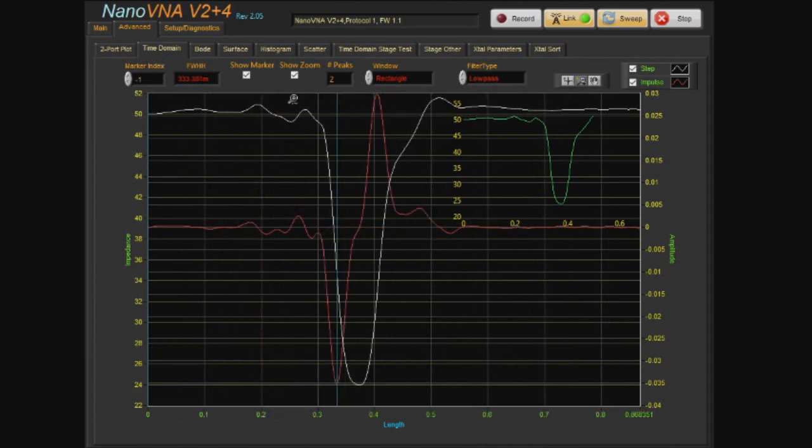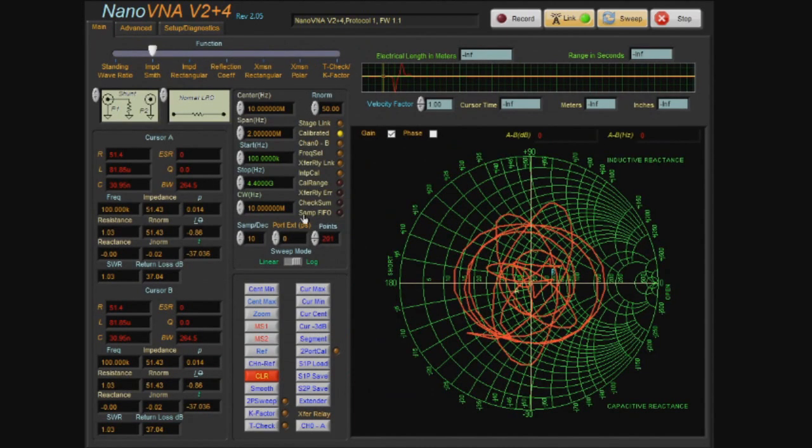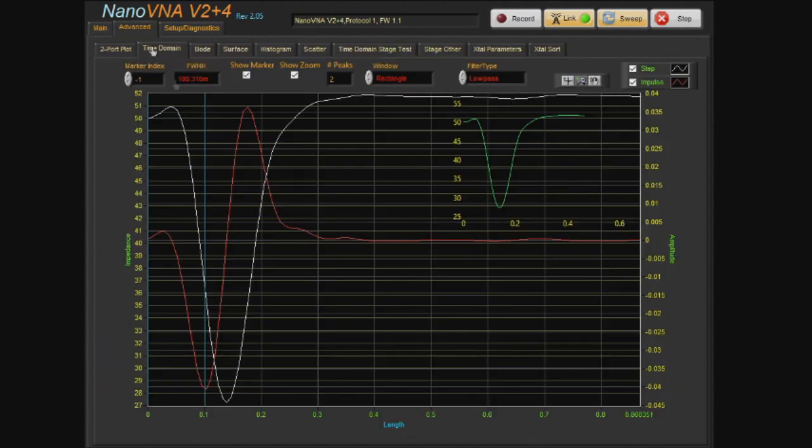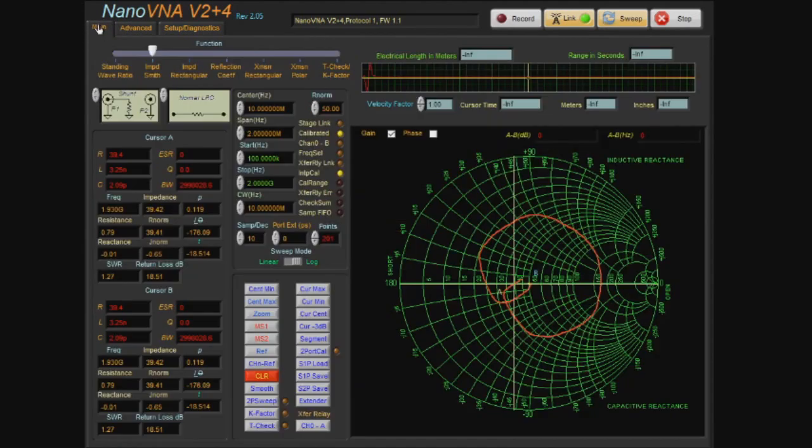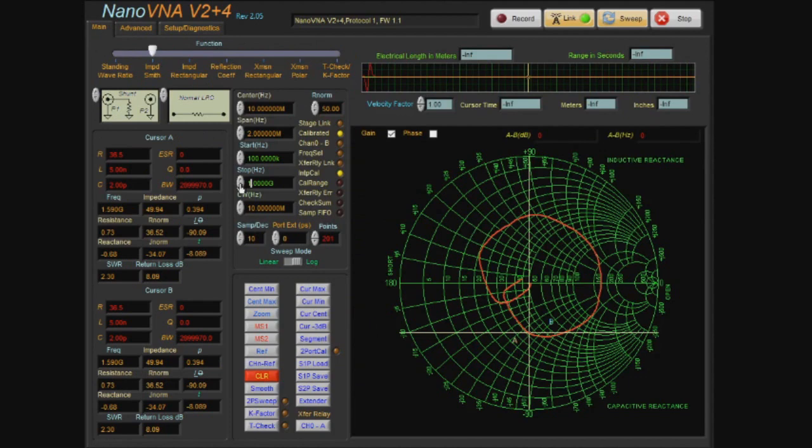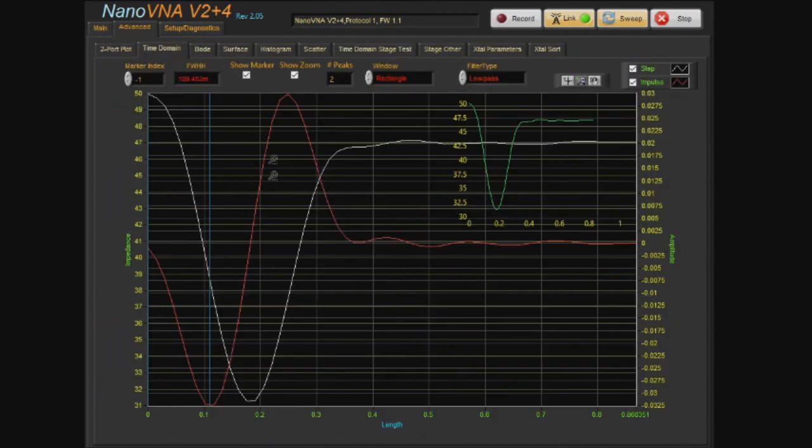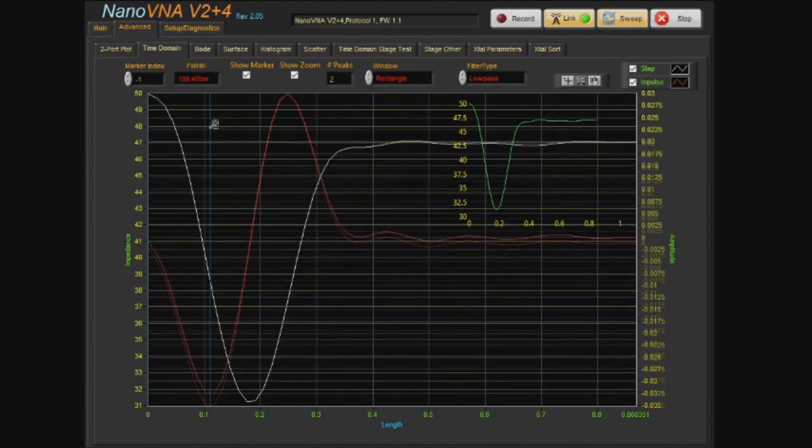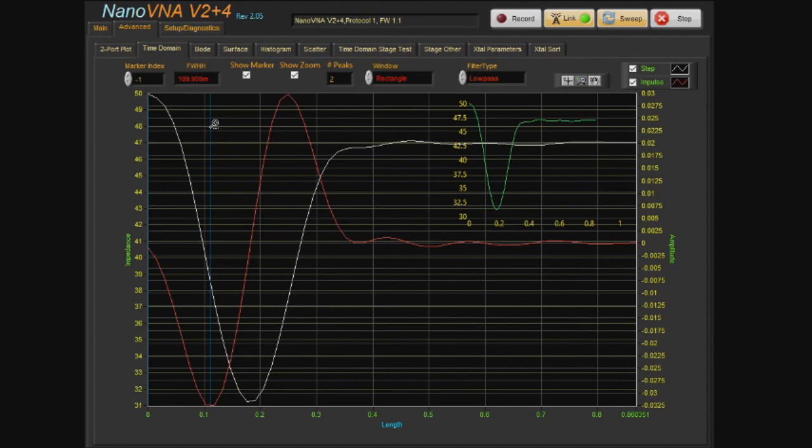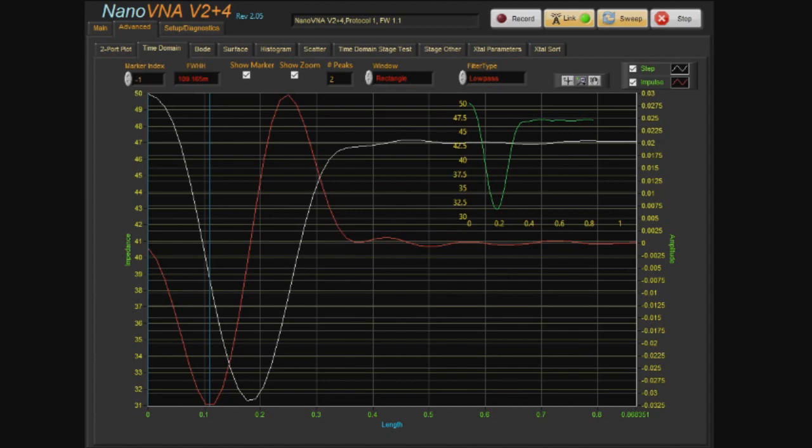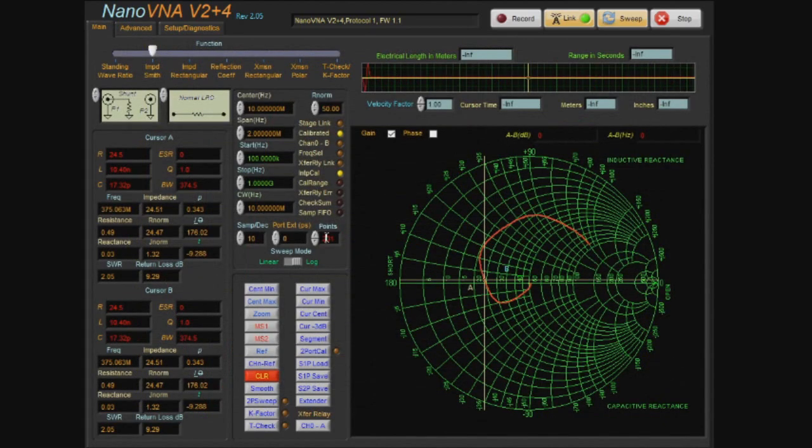Let's change our frequency to something much smaller, down to 2 gig. You see how that's really rounded off all these edges. We can go even lower to a gig, and now you can see it's really getting rounded. If you're trying to resolve very short distances, that's going to be a function of the sweep range, not the number of samples. If you really want to get sharp edges, you would want to get above even what this network analyzer is capable of. Maybe you want to be looking at like an 8720 or something. Something like that would certainly do a much better job of TDR measurement than the V2 plus 4.